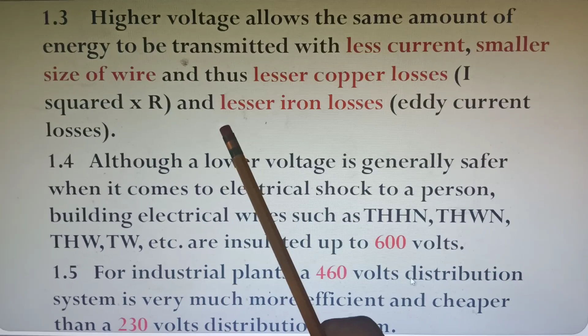Number 1.4. Although lower voltage is generally safer when it comes to electrical shock to a person, building electrical wires such as THHN, THWN, THW, TW, and so on, are insulated up to 600 volts. So that means that even if you have a 460 volt or 400 volt system in lieu of a 230 volt system, this kind of wires are very safe to use.